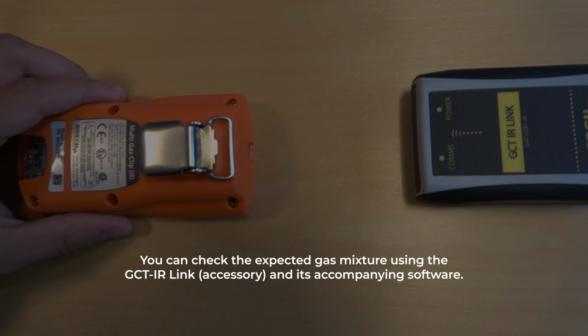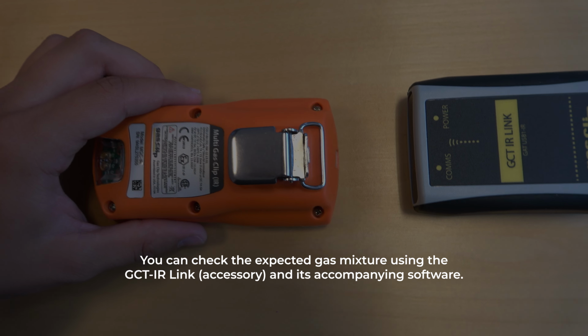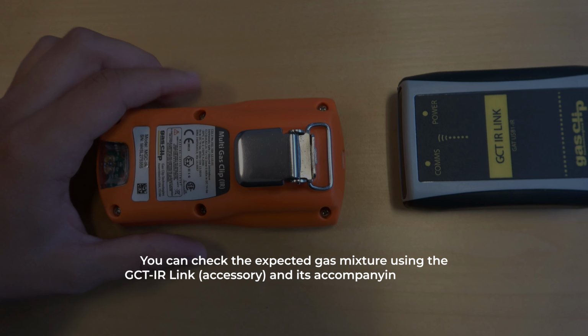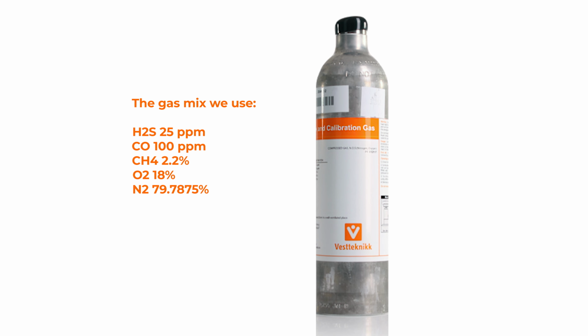If calibration fails, the gas in the cylinder may not match the values set in the MGC Simple Plus settings. You can check the expected gas mixture using the GCT IR link and its accompanying software. The gas mix we use: H2S, CO, CH4, O2 and N2.